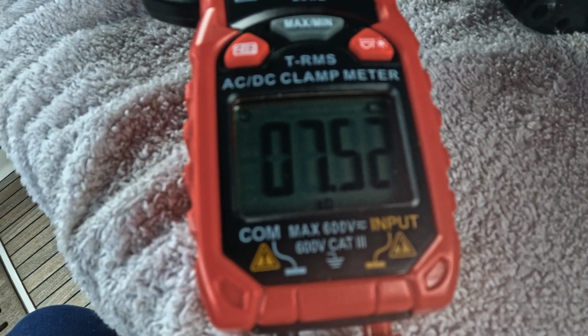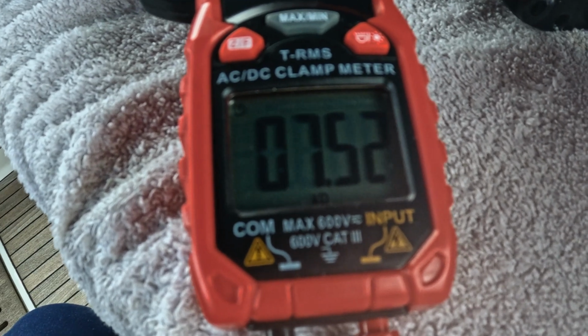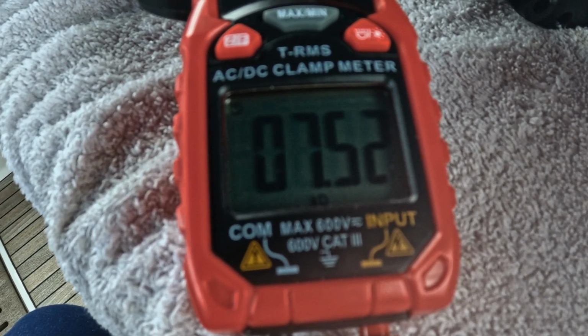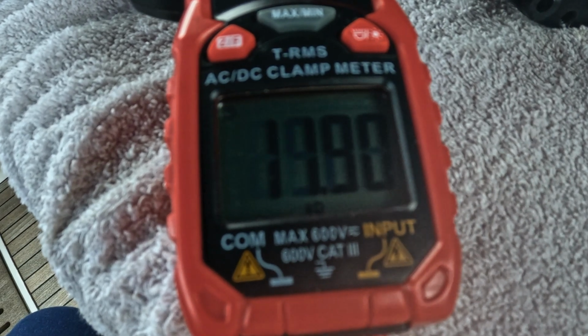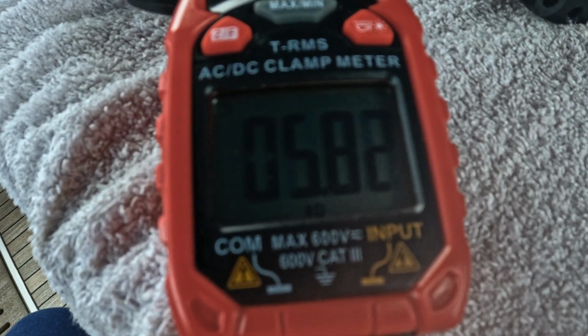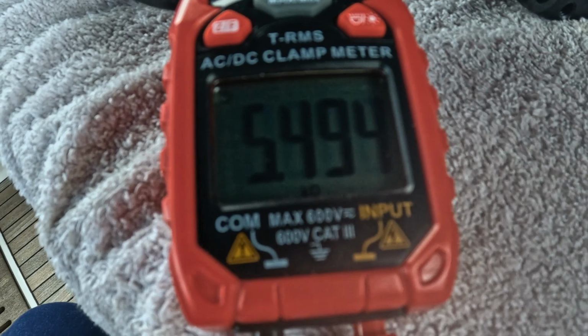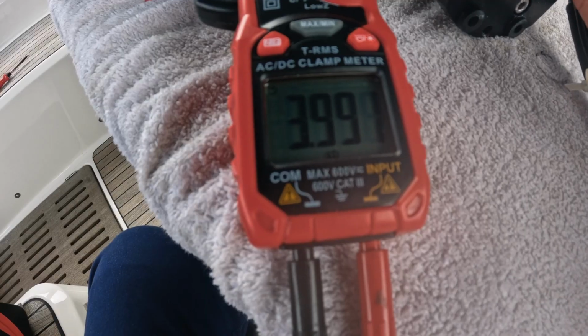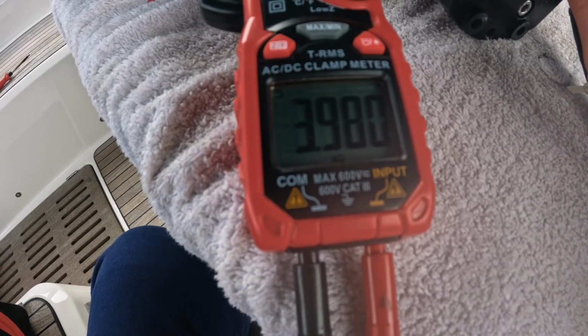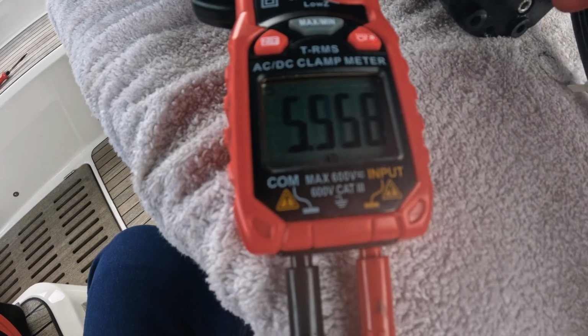Later, during editing, I noticed this part where it was going down, stalled at about 7.5k, then jumped up to 23k before dropping back to 5k, and this was with me turning the shaft in one direction only. This confirms the transducer has become electrically noisy and will need to be replaced.